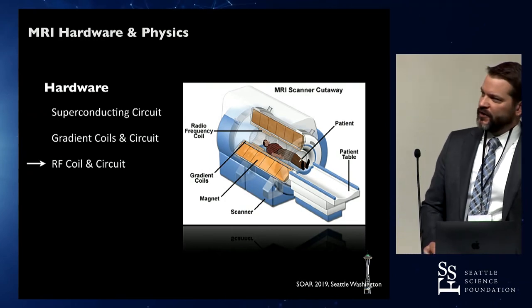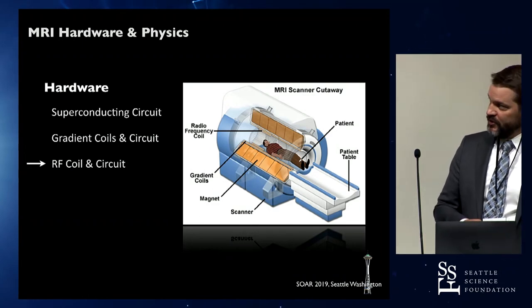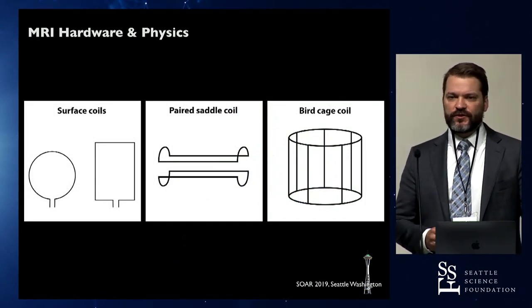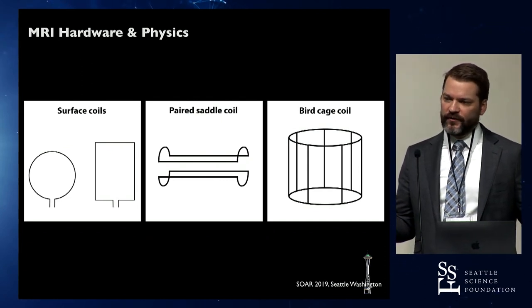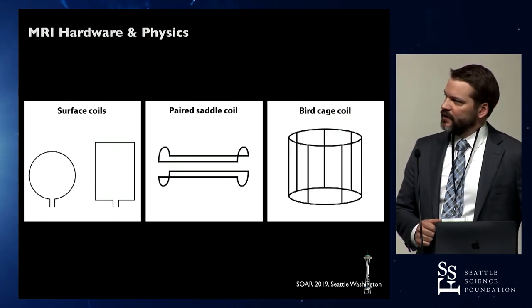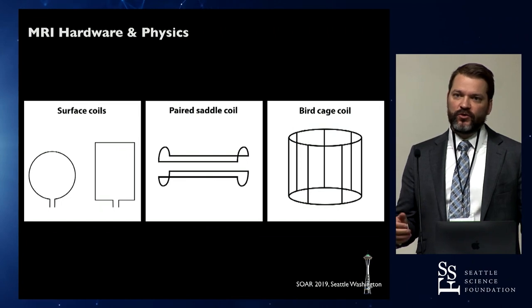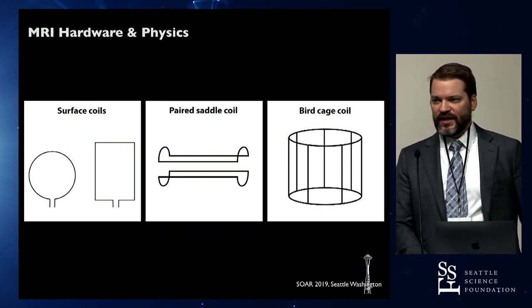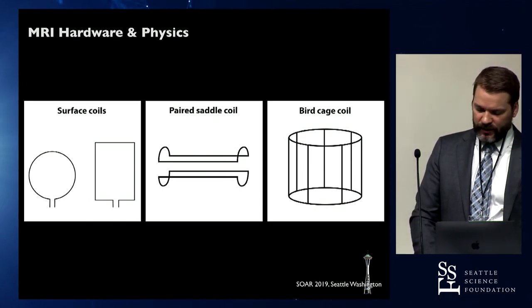The RF coils detect the differences in released energy when protons go from a high-energy state back to their natural state. You can have body coils and surface coils. Body coils are housed within the bore, farther from the body, so they give poor spatial resolution and require a stronger RF pulse to acquire data. If you put a surface coil or local coil on, it requires much less energy and you get better spatial resolution — which is why for head MRI we typically put a coil on.